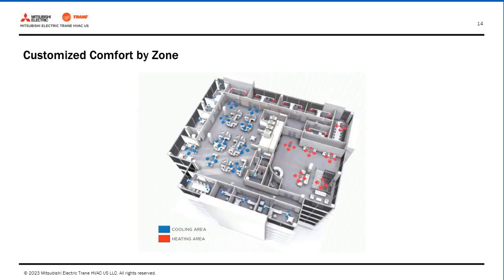VRF technology allows for indoor air temperature to be customized by zone. Most spaces that are in larger areas that may be served by rooftop units could have one rooftop serving 6 or 7 spaces, where one person is in control of the set point of that. So that's the huge advantage to VRF: you have the option for better zoning, and you can also do simultaneous cooling and heating, which we refer to as heat recovery.